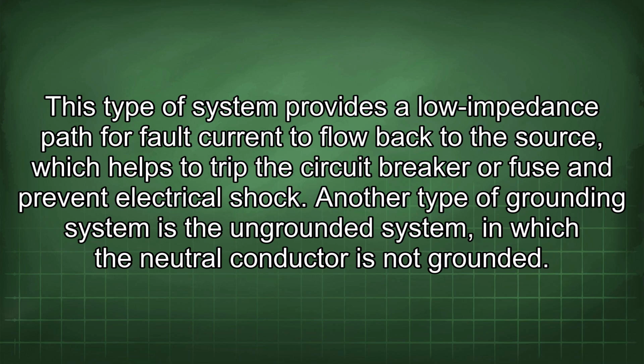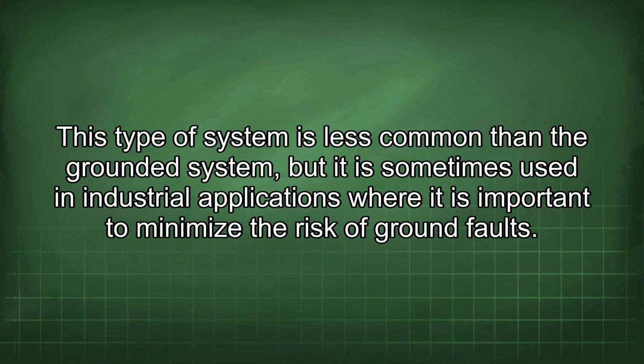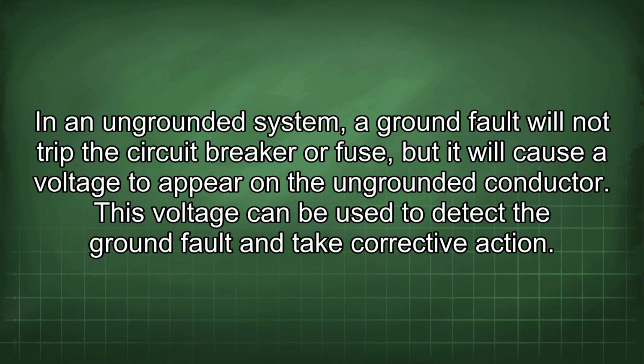Another type of grounding system is the ungrounded system, in which the neutral conductor is not grounded. This type of system is less common than the grounded system, but it is sometimes used in industrial applications where it is important to minimize the risk of ground faults. In an ungrounded system, a ground fault will not trip the circuit breaker or fuse, but it will cause a voltage to appear on the ungrounded conductor. This voltage can be used to detect the ground fault and take corrective action.